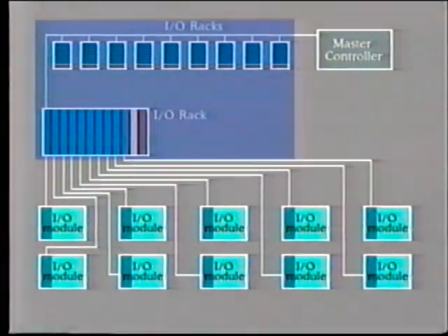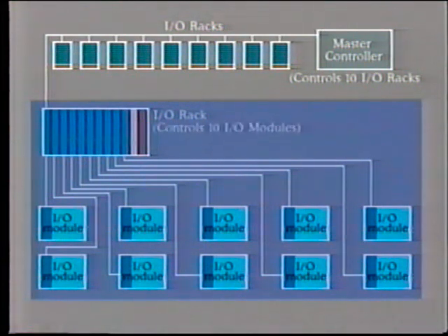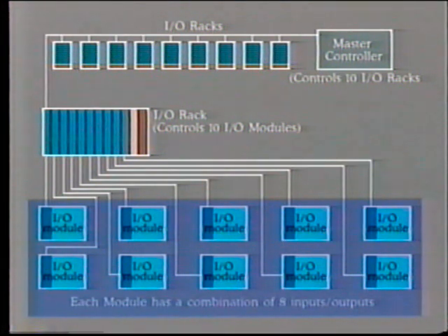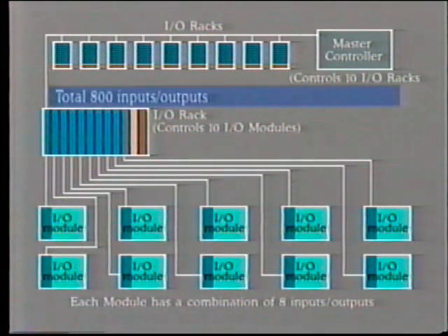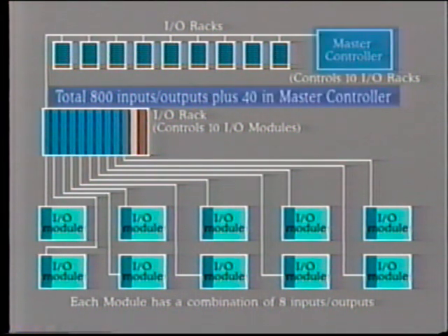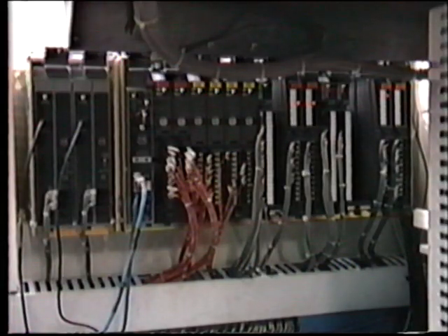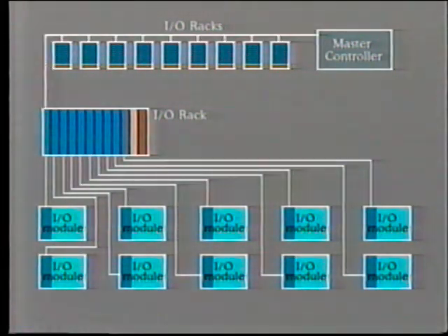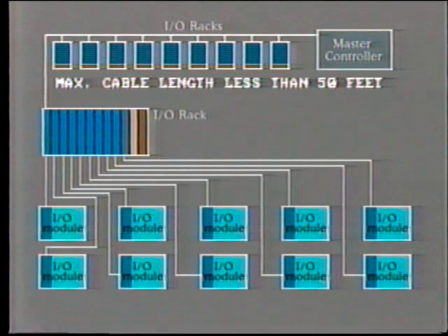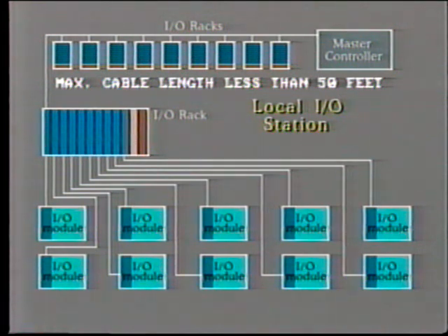For example, in this system, 10 I/O racks may be connected to the master controller, and each of these racks can control up to 10 input or output modules. So with each module containing 8 inputs or outputs, we can have a total of 800 inputs and outputs, in addition to the 40 or so contained in the master controller. Each of the I/O racks contains its own power supply, plus a receiver for communications with the master controller. All of the 10 racks can be connected on the same loop, providing that the maximum cable length is not greater than 50 feet. This arrangement is known as a local I/O station.